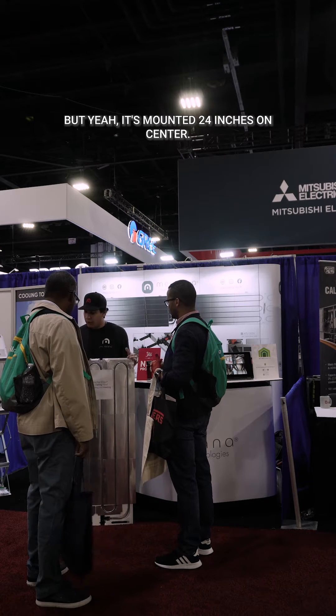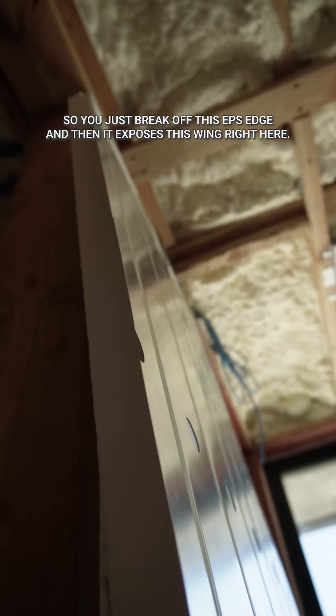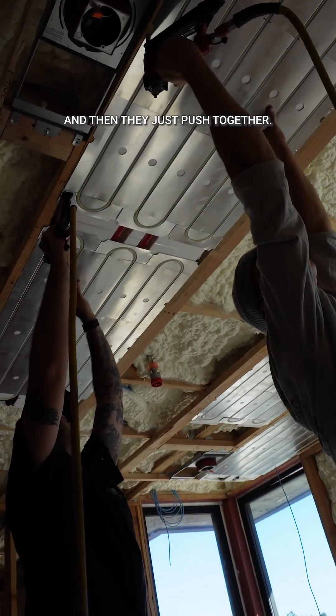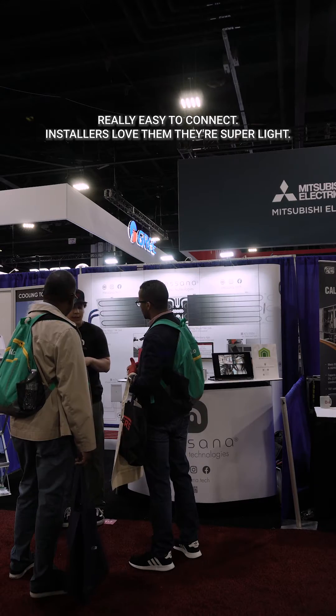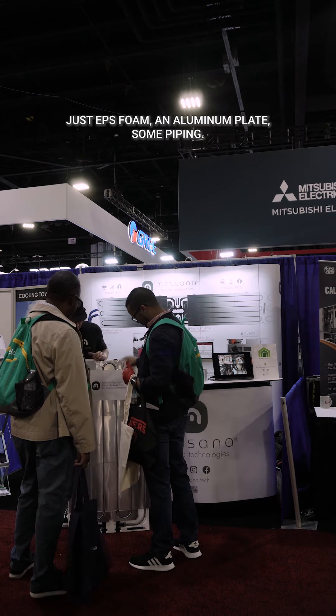It's mounted 24 inches on center. You just break off this EPS edge, and it exposes this wing right here — this is what's stapled or screwed up to your ceiling joists or furring channels. They just push together, really easy to connect. Installers love them, they're super light. It's just EPS foam, an aluminum plate, and some piping.